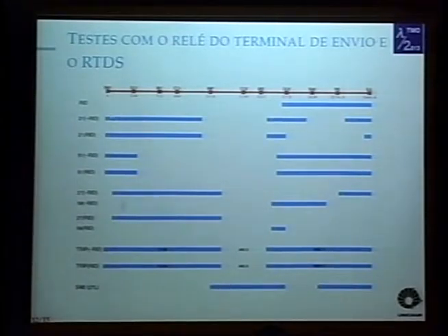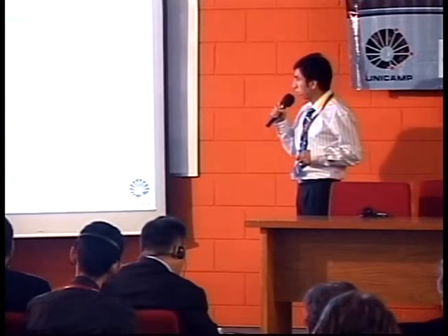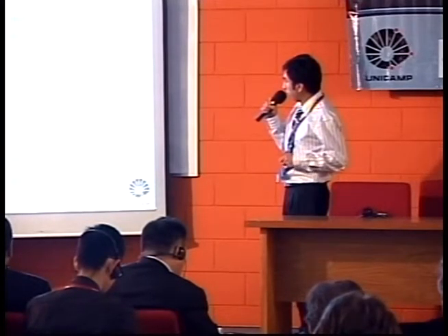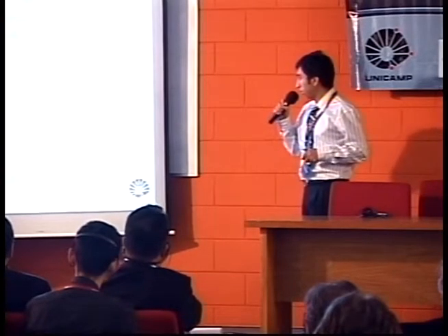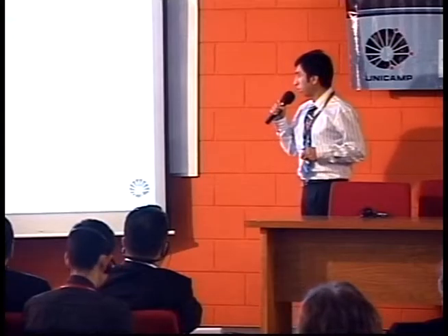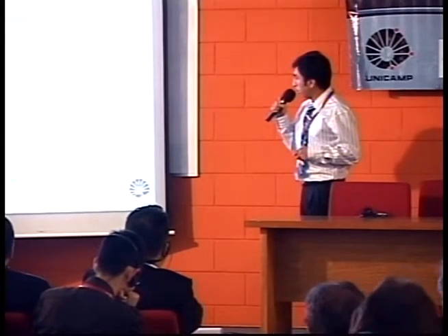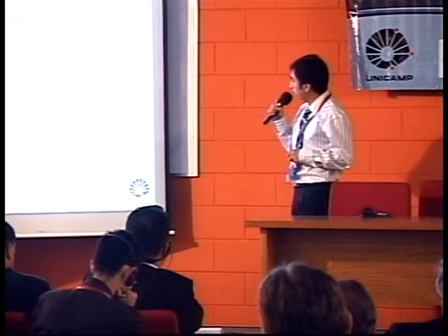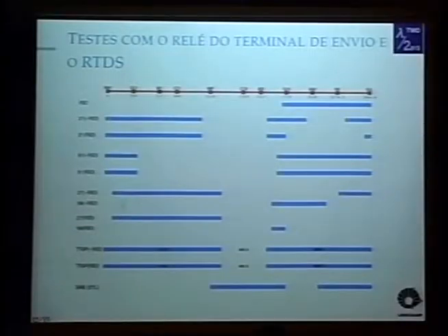And then we have the individual performance of the RID for voltage, current, and under and over voltage. On this line, the distance device is working without RID, and it starts working at the beginning of the line, as we said, zones 1 and 2, and then again after half the line, and also in the final segment of the line. When we include RID, the performance at the beginning of the line does not change, but in this segment, because RID is working, it removes impedances from the protection zones, and we do not have the distance device working anymore, except in the final points, which is a little bit more than half a wavelength.